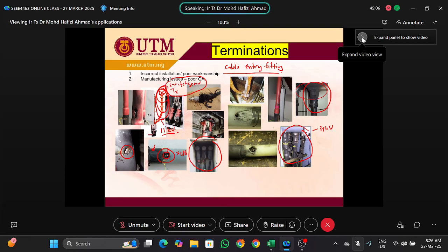But now you can see, because of the installer, the cable jointer - for your information, for medium voltage we have PK1, PK2, and PK3. PK1 can install cable below 1 kV, PK2 can install below 11 kV, and PK3 can install below 33 kV. So basically PK1 can install low voltage cable, I mean 400 and 500 volts.